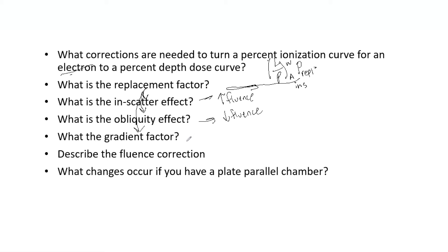The gradient factor is the displacement, an effective point of measurement. This is equal to 0.5 R cav. Now this is a radius of the air cavity, not just the radius of the chamber itself. That is of course dependent on the cavity radius, mean energy, and the gradient factor. And again, all these are in P replacement.